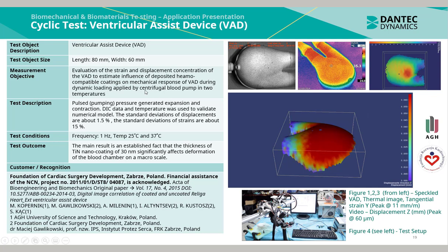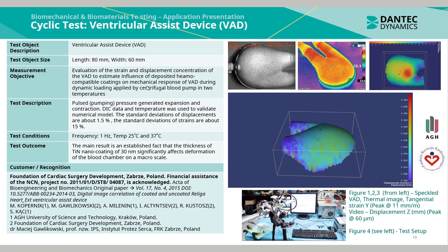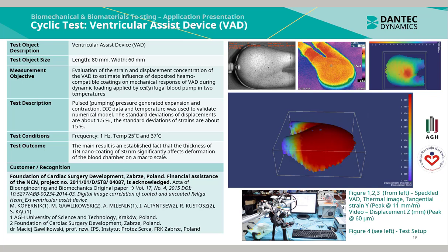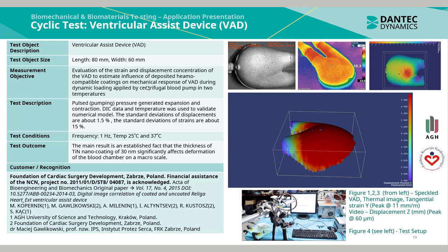The measurement objective is to evaluate the strain and displacement concentration of the VAD, to estimate the influence of the deposited hemo-compatible coatings on mechanical response of the VAD during the dynamic loading, applied by using a centrifugal blood pump in two temperatures.